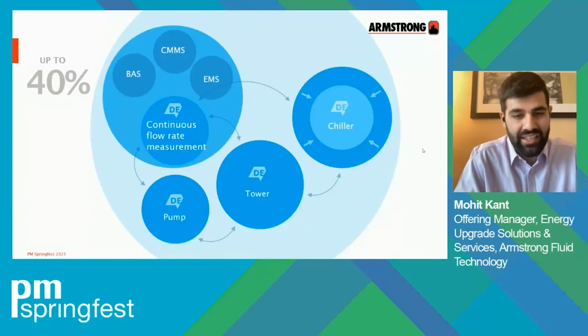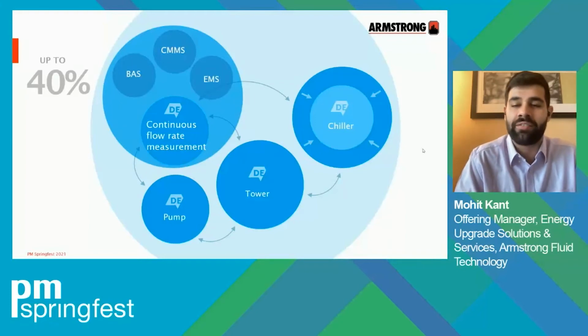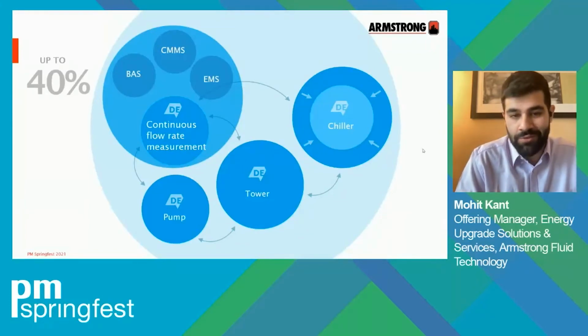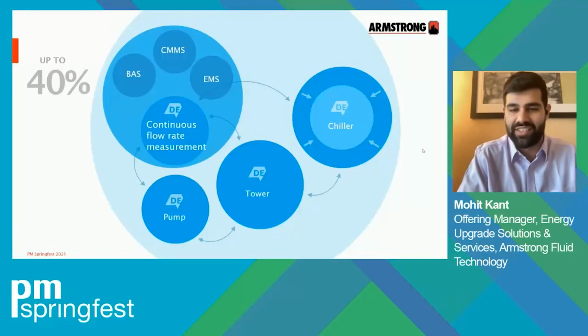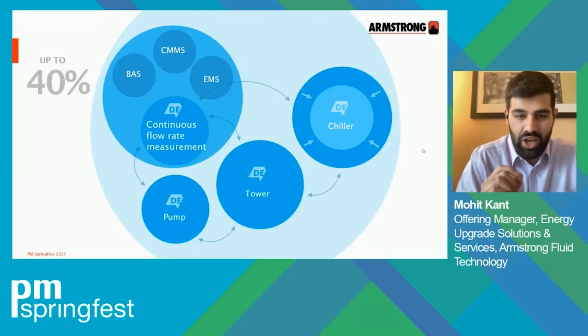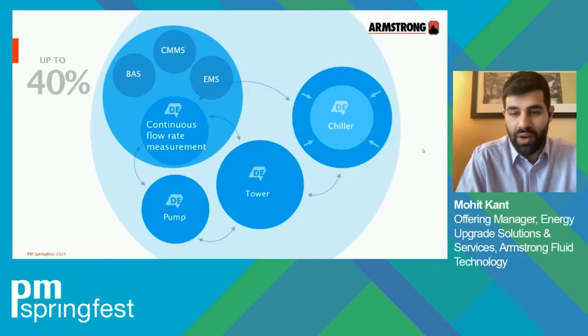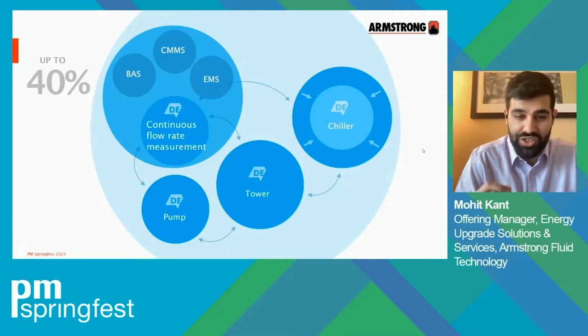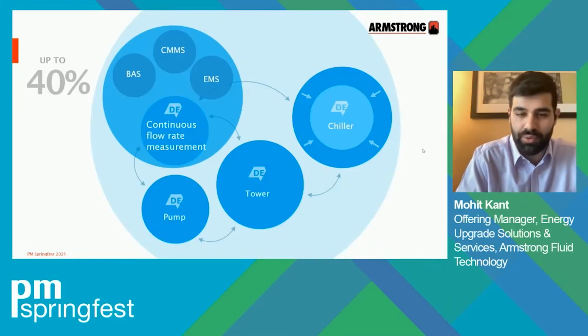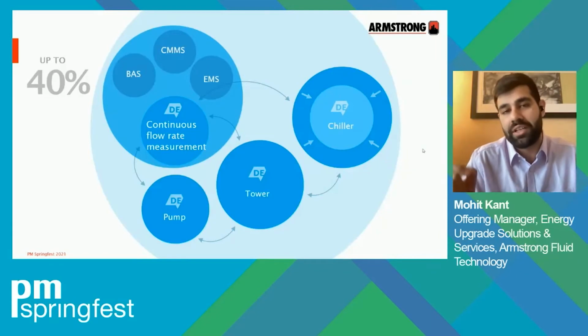In practice, we see that plant systems are often oversized. In an upgrade, the tendency is to replace with like-for-like capacity, while building demands have changed over time, occupancy has changed, and internal loads have reduced from lighting upgrades and other advances in technology. Add to these the tendency to apply safety factors, which further adds to oversizing. With a pump-first approach, the optimal path to a plant upgrade is assessing the transparent information to right-size the plant and achieve optimum efficiency, not only delivering up to 40% energy savings, but also reducing capital upgrade costs by as much as 20 to 30%.